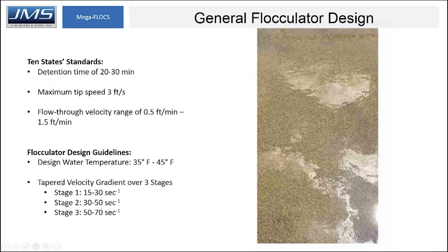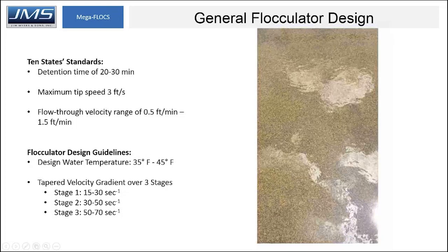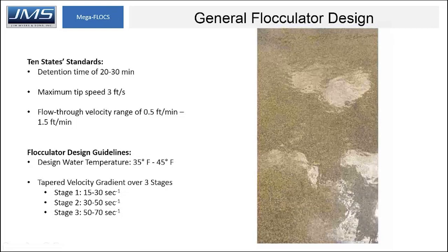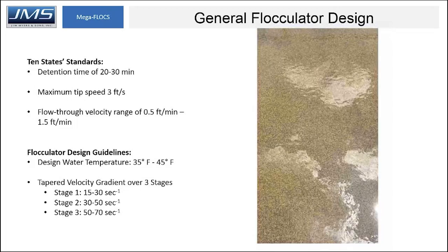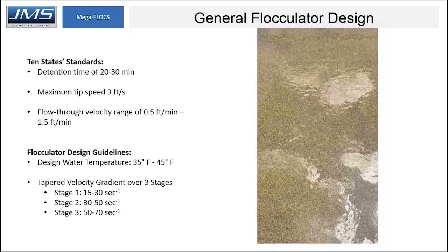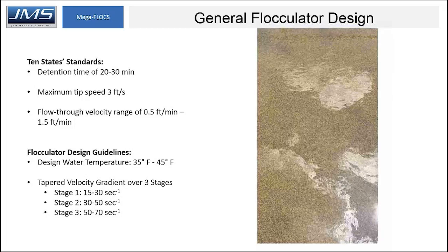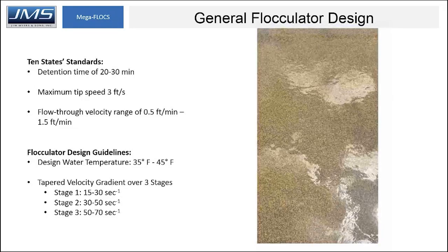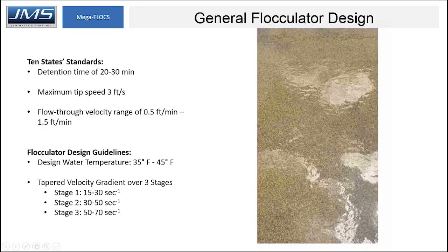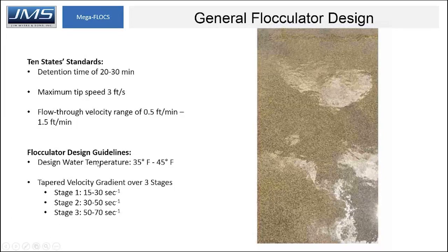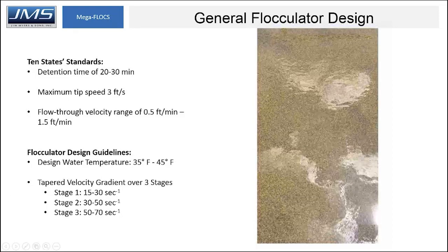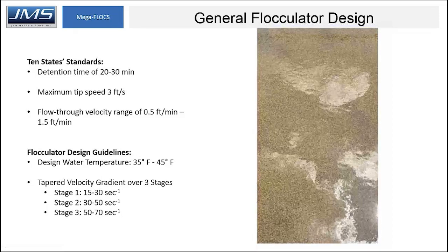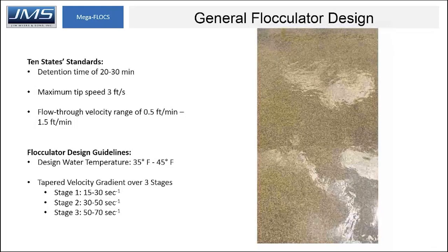The Ten State Standards are guidelines created by a group of states and Canadian provinces around the Great Lakes, and JMS paddle wheel flocculators are fully compliant to these standards. Three main points are that retention time should be between 20 and 30 minutes, maximum tip speed should be 3 feet per second or less, and the flow-through velocity of the basin should be 0.5 to 1.5 feet per minute.